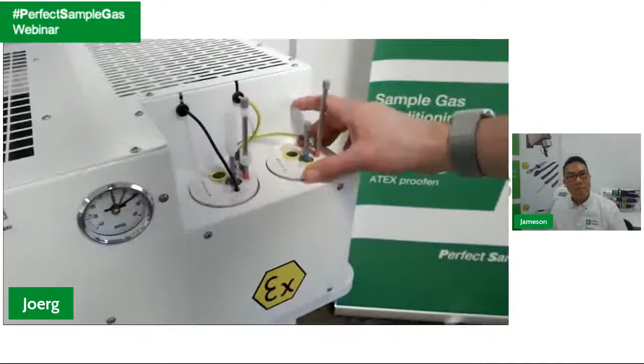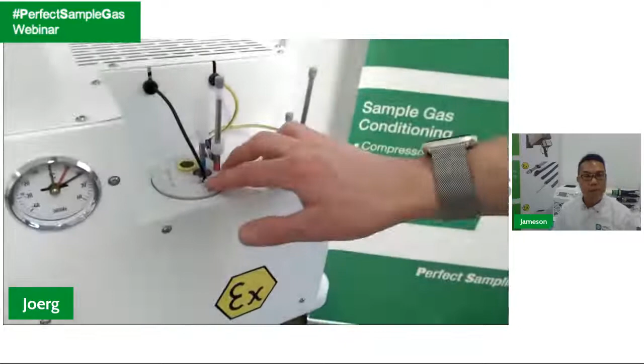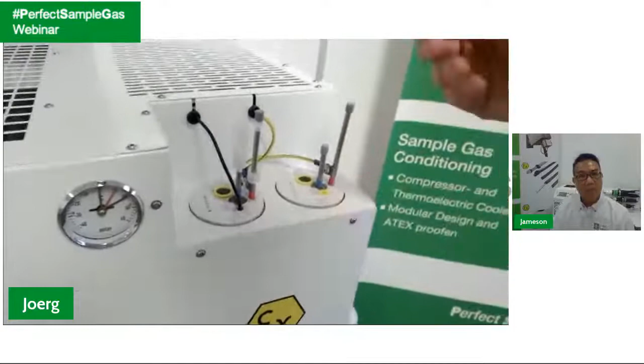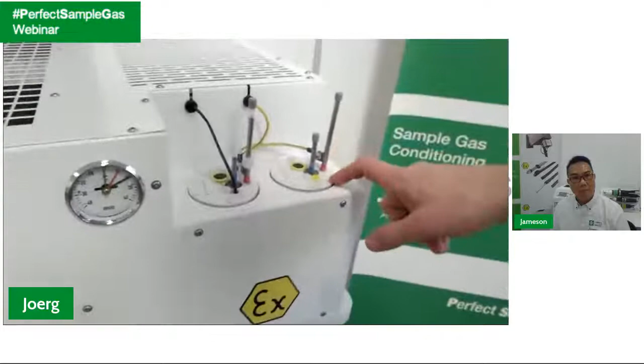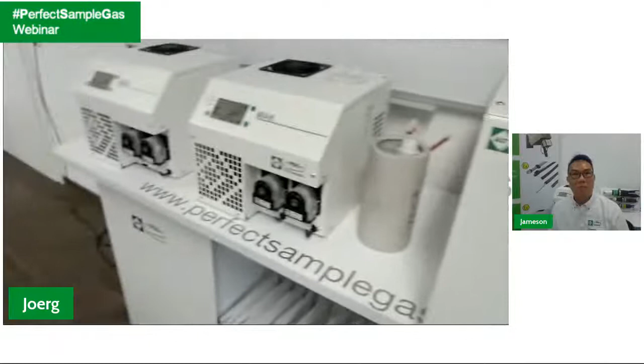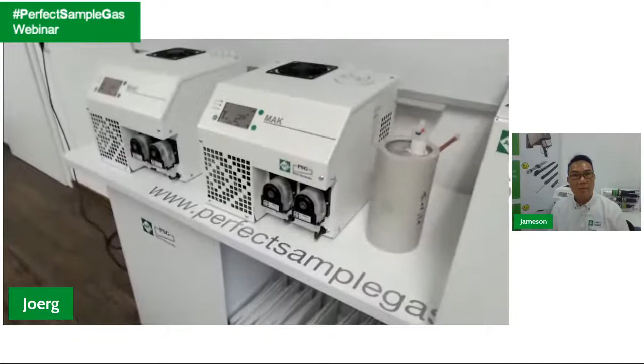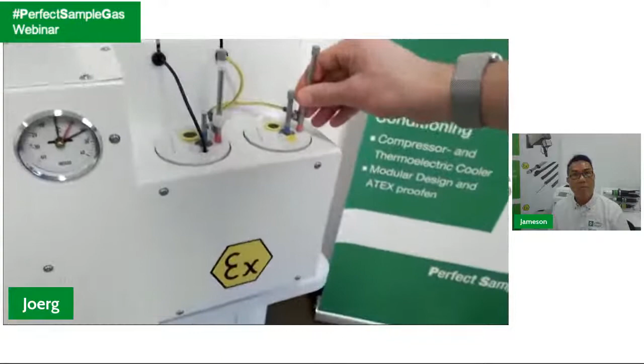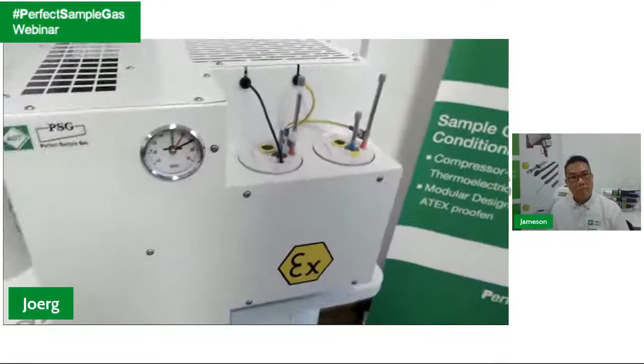In many situations in our standard SAM system, we will be sucking the probe. But in process analytics, it's relatively common in many applications that we would have positive pressure - pressure in the heat exchanger. Different to the two other models we will talk about, the MAK10 and the MAK20, we would have a version in stainless steel, and that would allow us to operate the cooler even with positive pressure.